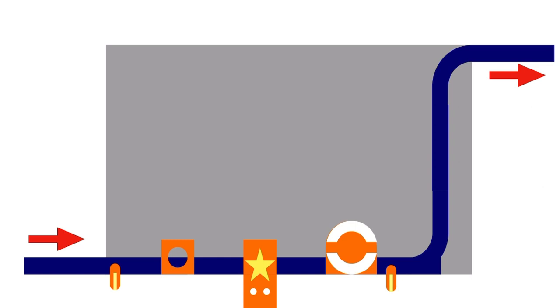So here's my simplified drawing of a multi-function valve. And we'll go through the valve from the time the gas goes into the valve until it leaves to go to the burner. So it's going to go in at the bottom left and it's going to go out to the burner at the top right. So the first thing that you're going to see there, sticking out of the valve, is an inlet pressure test point. I'm going to show you some photographs in a minute and you'll see exactly where these are on a couple of different valves.